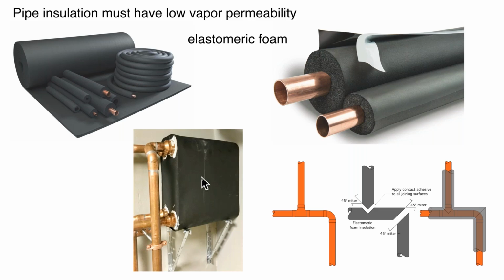Here's a plate heat exchanger that's been wrapped in a sheet. This is 1/2 inch thick sheet, and it's been glued together with contact cement. The entire heat exchanger, and eventually all this piping, will be insulated as well. So again, you really can't cheat, so to speak, when you're doing chilled water piping insulation.